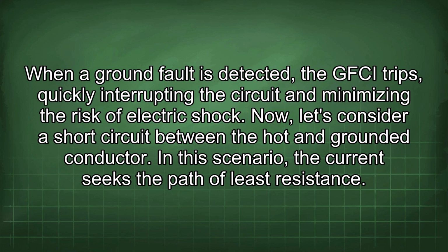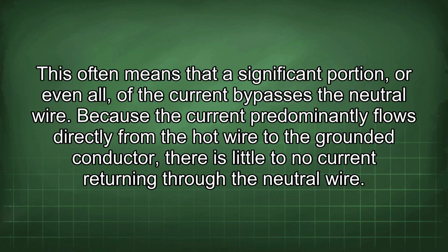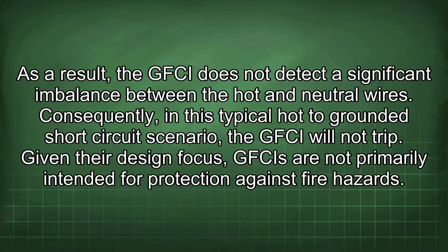Now let's consider a short circuit between the hot and grounded conductor. In this scenario, the current seeks a path of least resistance. This often means that a significant portion, or even all, of the current bypasses the neutral wire. Because the current predominantly flows directly from the hot wire to the grounded conductor, there is little to no current returning through the neutral wire. As a result, the GFCI does not detect a significant imbalance between the hot and neutral wires. Consequently, in this typical hot to grounded short circuit scenario, the GFCI will not trip.